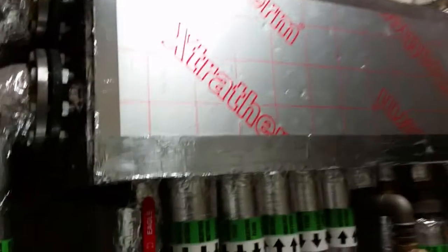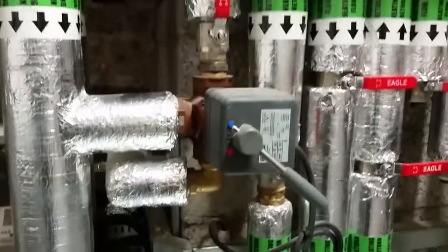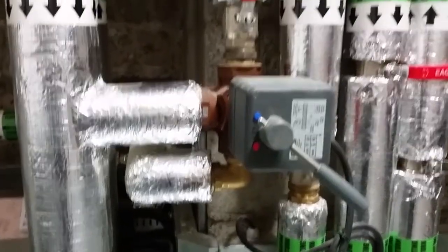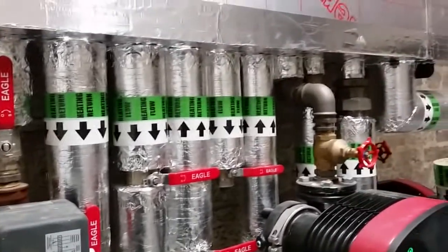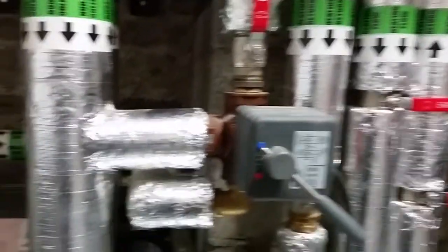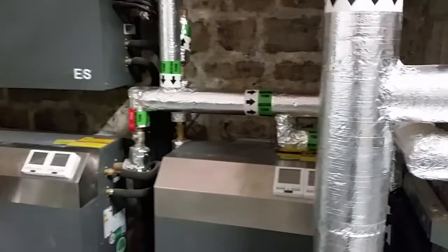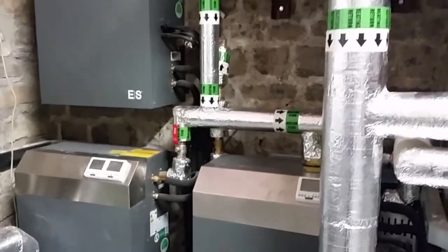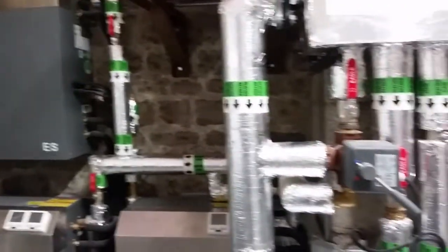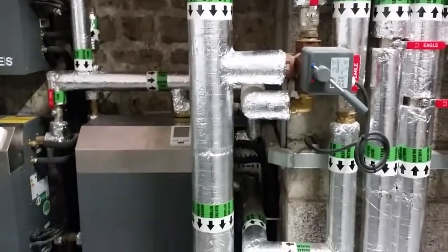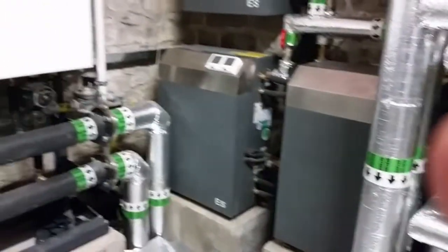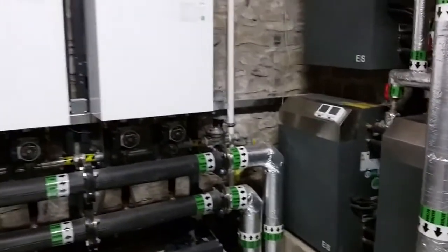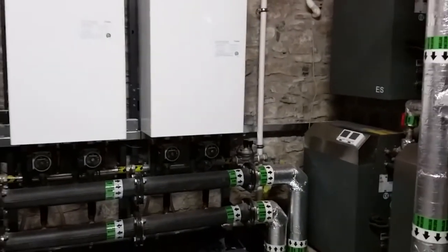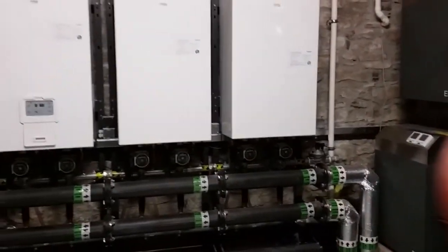In position 2, it will allow for the heat pump's output to flow to catch on the return water coming back from the zones and divert it through the heat pumps to preheat it. And when it's preheated, to introduce it back into the return of the gas boilers. So therefore, the heat pumps are operating at all times at maximum efficiency, either delivering heat or preheating the return water to the gas boilers.